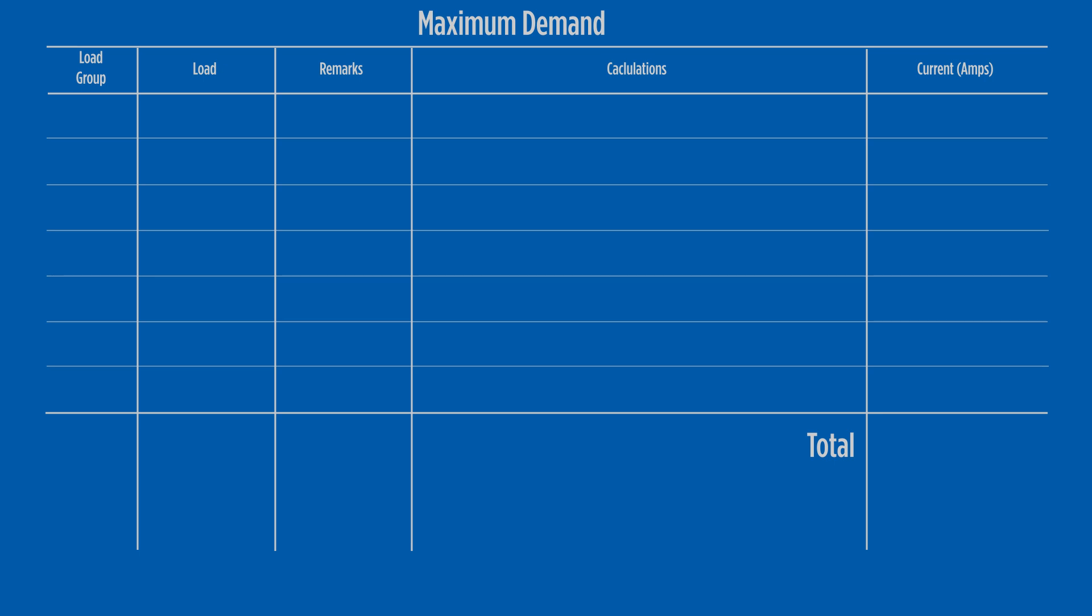The 24 lighting points will go into load group A1, as does the 10 metres of lighting track. Note 4 of table C1 states every metre of lighting track equals two points. This means the 10 metre track contributes 20 points. Note 5 states that loads above 2.3 metres up to 150 watts can be included in load group A1 as a point. The 50 watt exhaust fan fits into this group, giving us a total of 45 lighting points in the A1 load group.